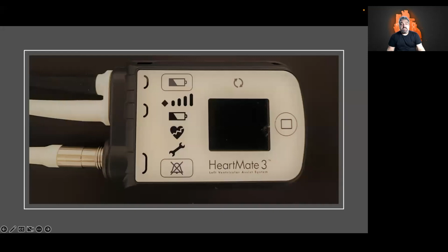This is the VAD controller. This is the button that silences the alarms, and this is the button that toggles between the different screens on the VAD. So when you push it, it's going to switch between RPMs, flow, power, etc. If you push both of those buttons together, it's going to show you the most recent several alarms, and you can scroll through them because that's another piece of information the VAD coordinator may want from you.